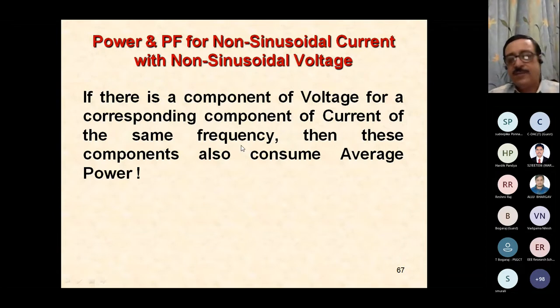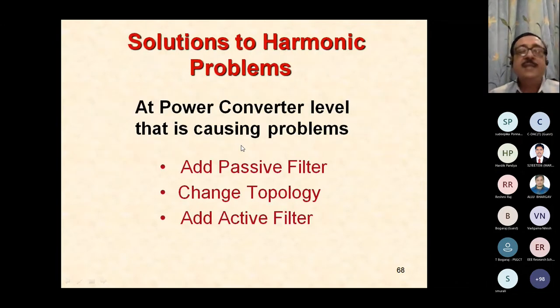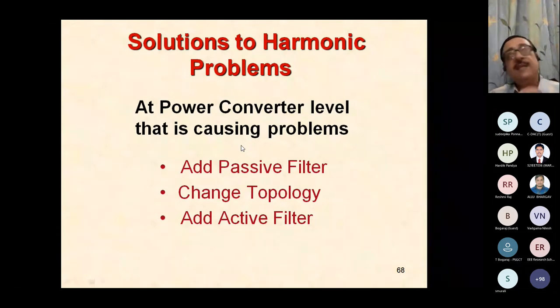I have said sinusoidal voltage and sinusoidal current of the same frequency. I didn't say what frequency, they have to be the same. So if there is a harmonic component in the voltage and a harmonic component in the current of the same frequency, there will be power consumption. How do we tackle this power problem, this harmonic problem? Our power electronic systems are injecting harmonics.